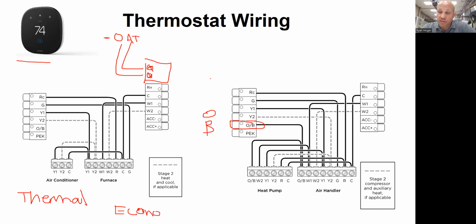So yes, you can get a heat pump that'll do that, but that system is going to be significantly physically larger than your existing system with gas heat. You're going to need a lot of coil surface area to do that. So that would not be a clean change out. That would be a throw everything I have in the trash, except my ductwork, buy everything new. It wouldn't be like one of these change outs we're talking about here. It would be much more involved.